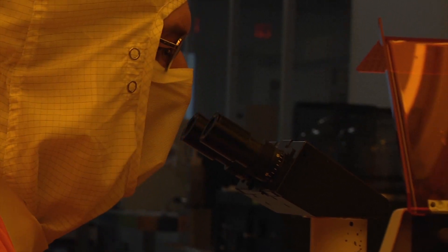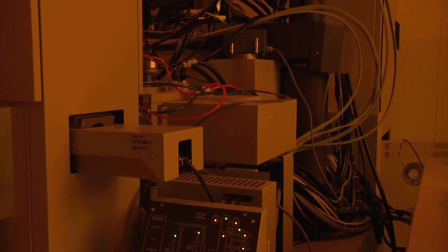About 40% of the clean room is the old Class 10, ISO 4. And then the remaining areas — which are primarily aisle, about 15% of the room — tool cleaning areas and things like that — are ISO Class 5, or the old Class 100. That makes us much cleaner than other university clean rooms in the country.